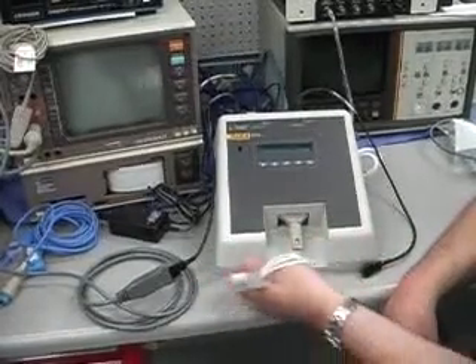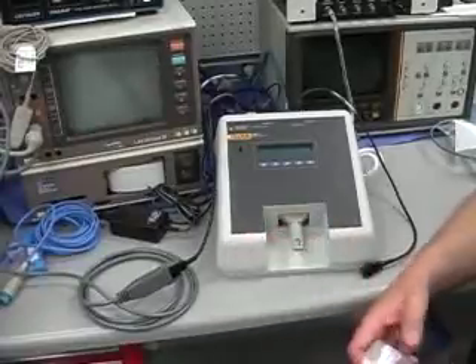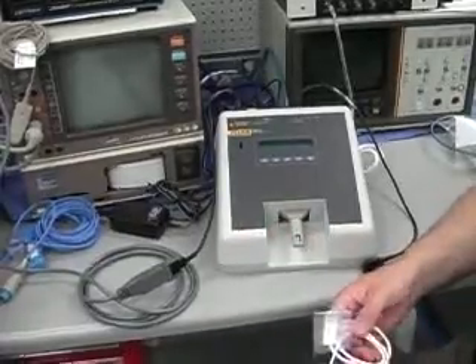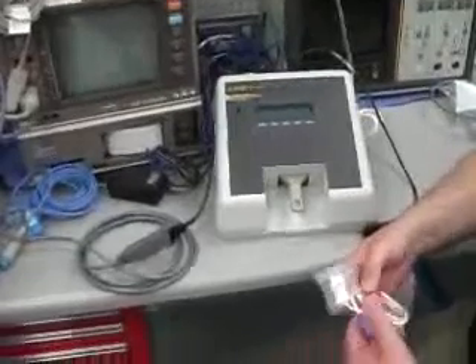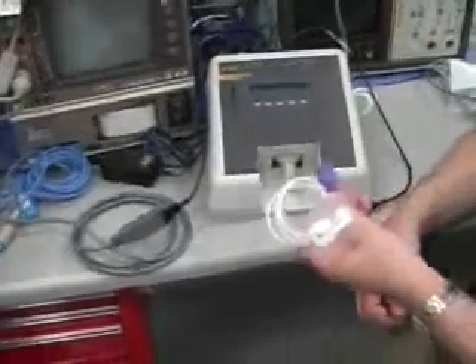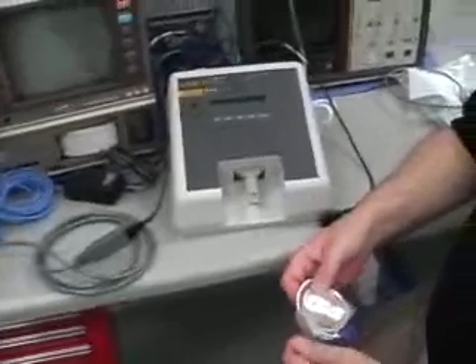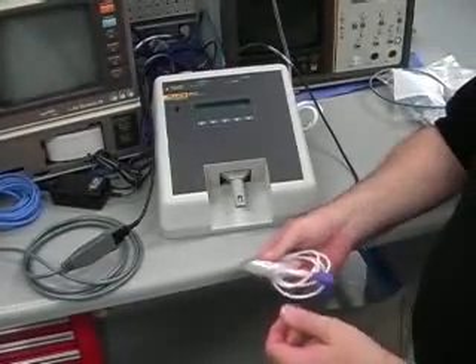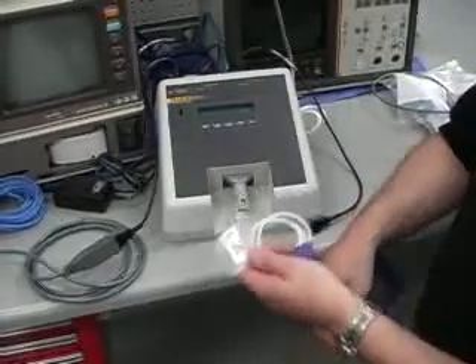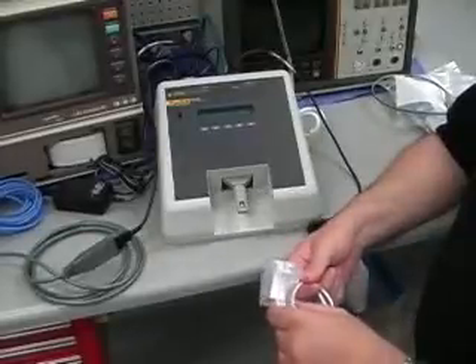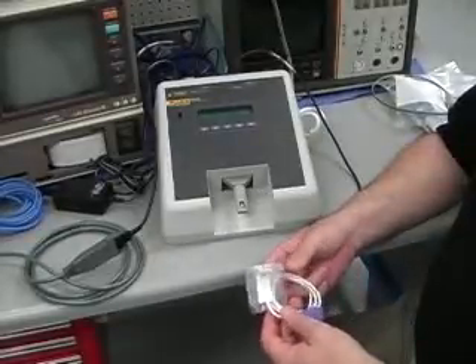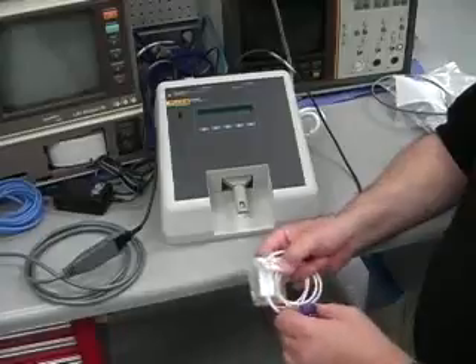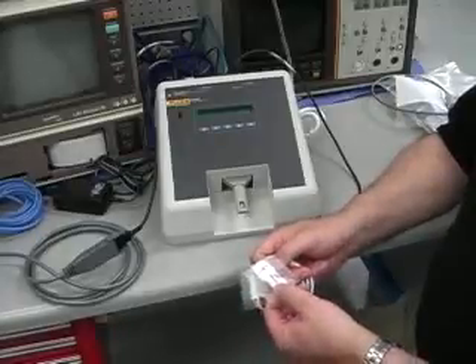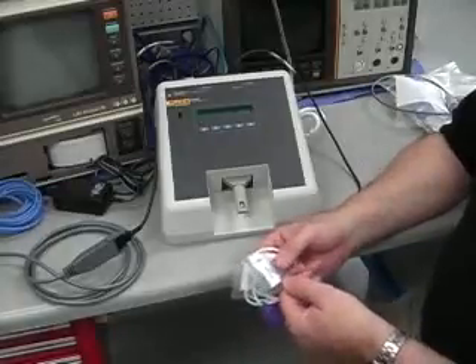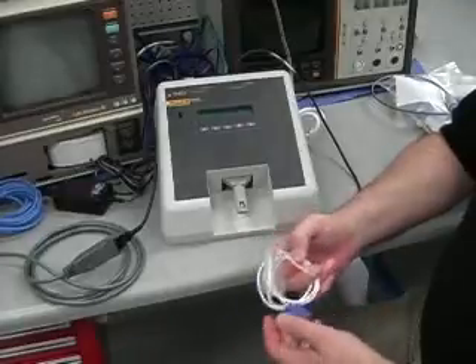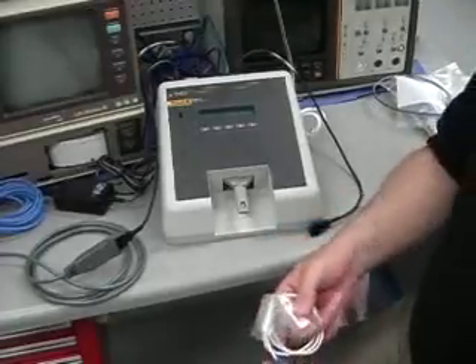So if you just have the equipment to test, this is a good way to do it. If you're looking at troubleshooting a system that's in the field, it's best to verify with a reusable probe. In the case of the Nellcor, the DS100 would be the better one to use. The calibration curves for the MaxAL are very similar to that of the DS100, so we shouldn't really have any major problems.